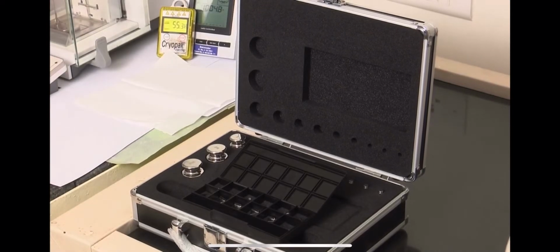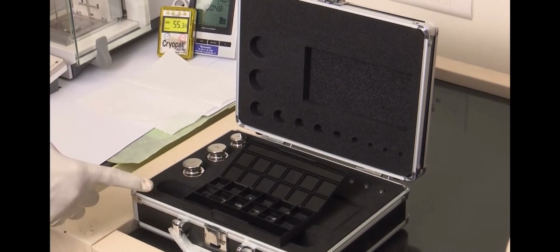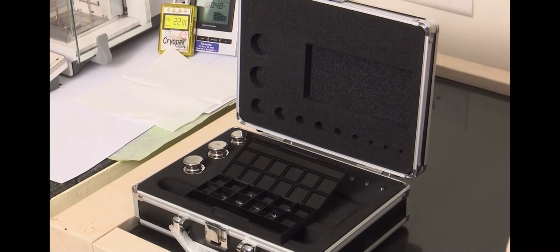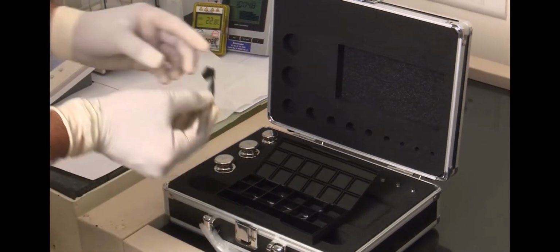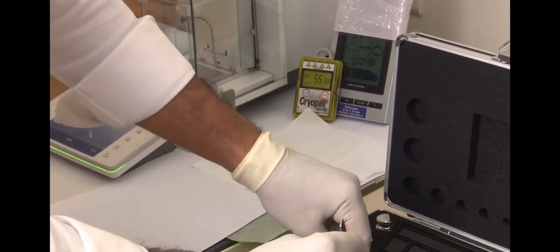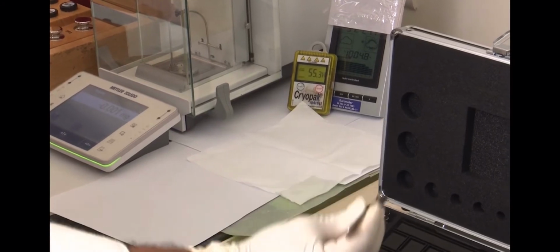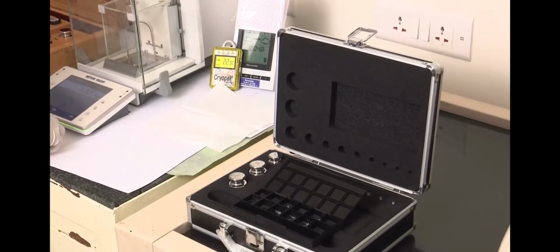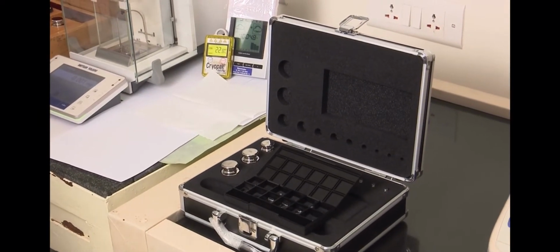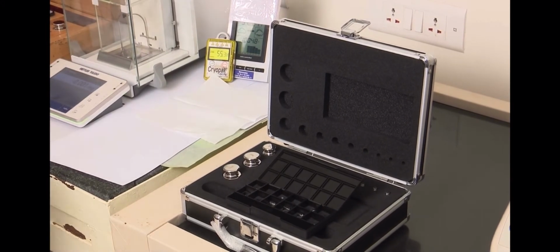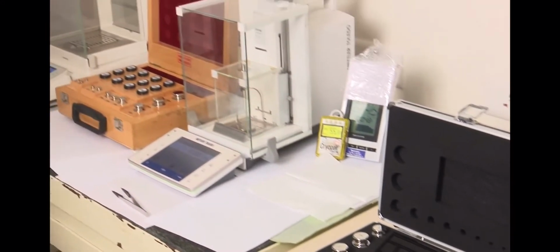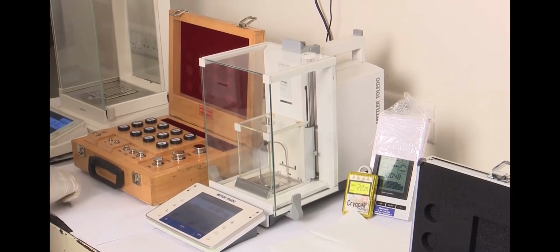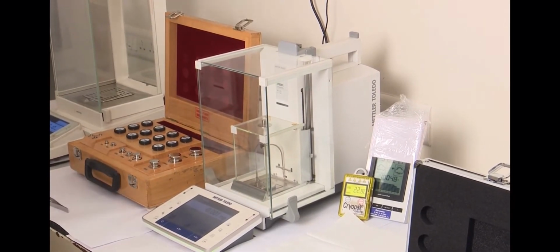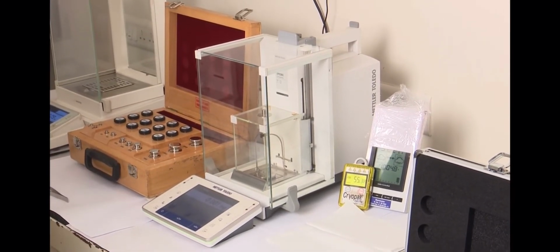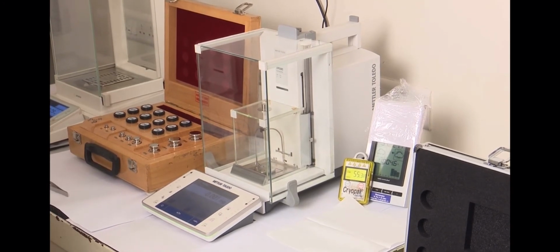Here I am demonstrating live display of step-by-step calibration method for weight. After cleaning, visually inspect the weight for shape as per OIML R111 Part 1 and rust etc. Keep the weight for thermal stabilization as per OIML R111 Part 1 at 23 plus minus 0.5 degrees centigrade so that the temperature is brought to equilibrium.